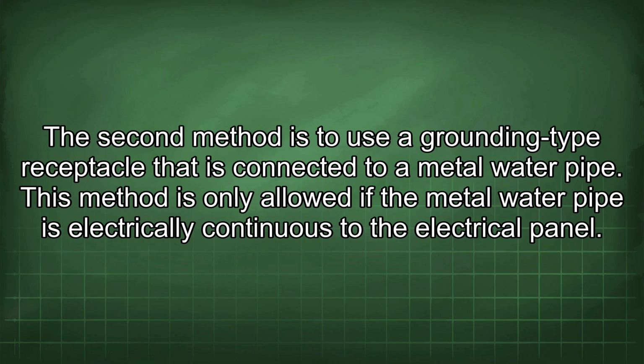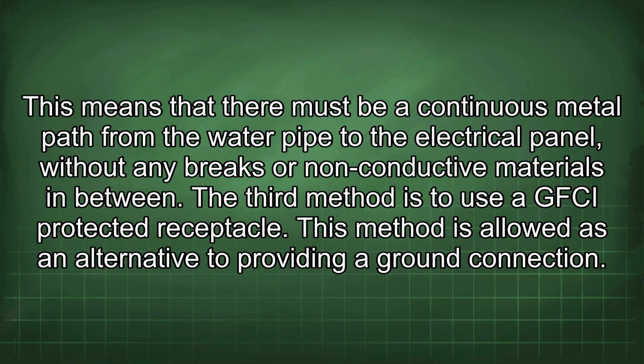The second method is to use a grounding type receptacle that is connected to a metal water pipe. This method is only allowed if the metal water pipe is electrically continuous to the electrical panel. This means that there must be a continuous metal path from the water pipe to the electrical panel, without any breaks or non-conductive materials in between.